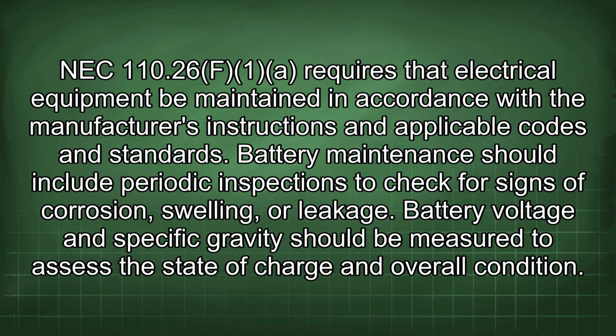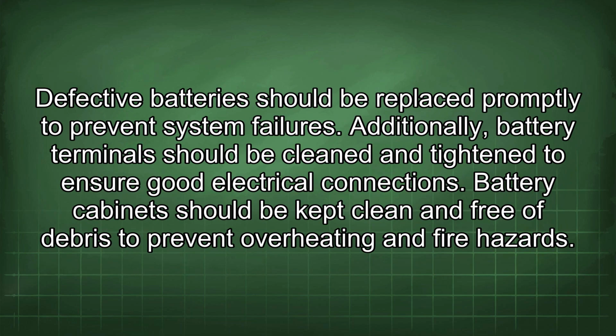NEC 110.26 requires that electrical equipment be maintained in accordance with the manufacturer's instructions and applicable codes and standards. Battery maintenance should include periodic inspections to check for signs of corrosion, swelling, or leakage. Battery voltage and specific gravity should be measured to assess the state of charge and overall condition. Defective batteries should be replaced promptly to prevent system failures.